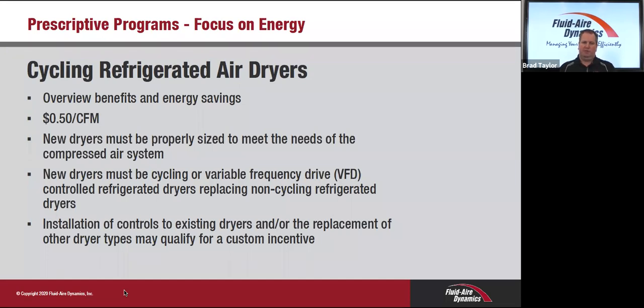The way these two types of energy saving technology work, specifically the cycling type, is it uses some type of thermal mass, whether it's sand or a glycol solution in a tank, or there's even technology that uses ice. The concept is that it operates much like your refrigerator or air conditioner at home: once the temperature has been achieved in the thermal mass, we can shut off the refrigeration circuit to conserve energy. Then as that thermal mass warms up, we can bring that refrigeration circuit back online.